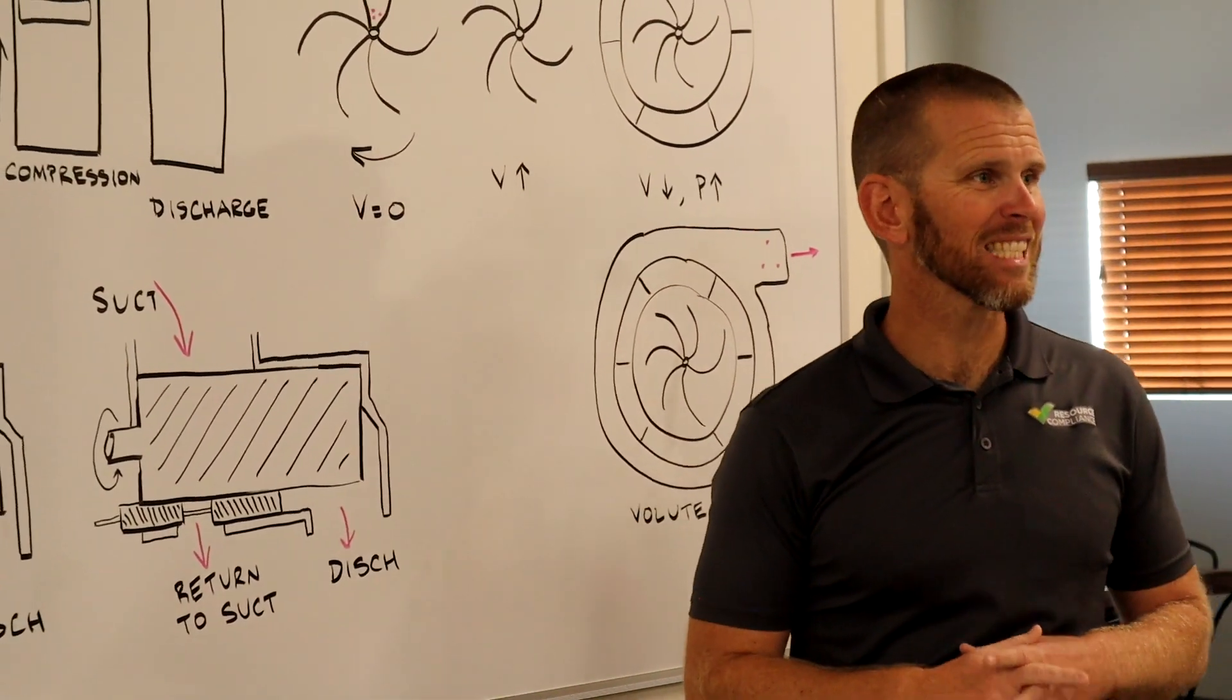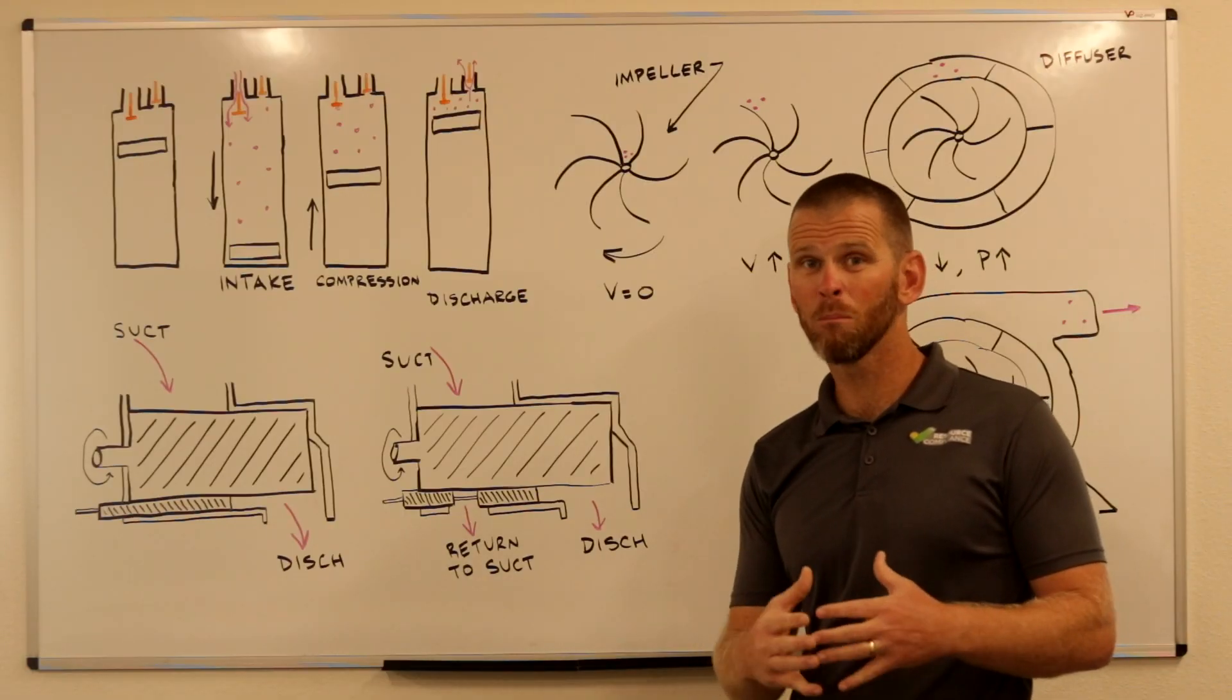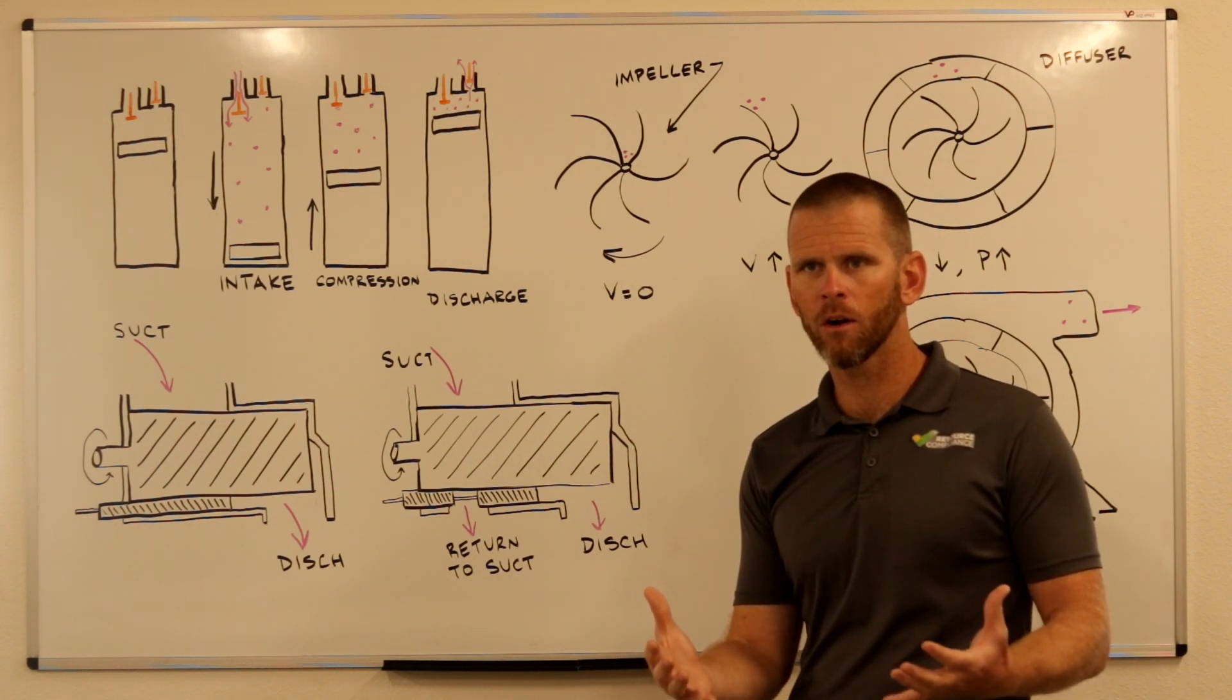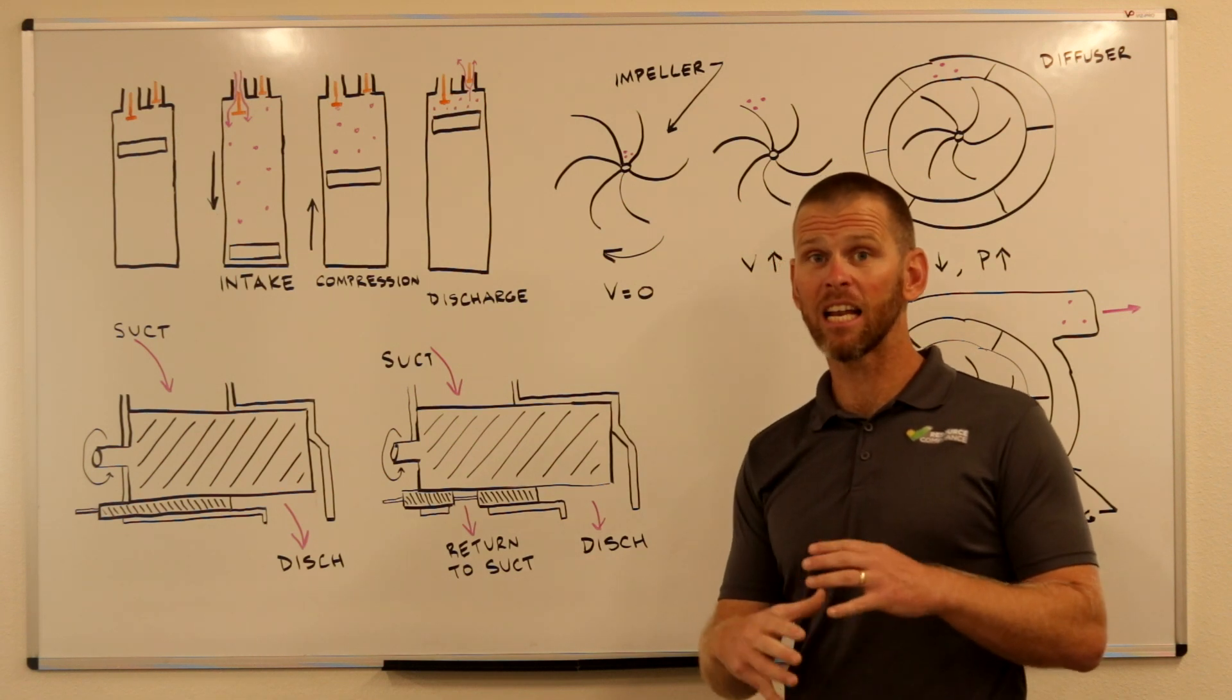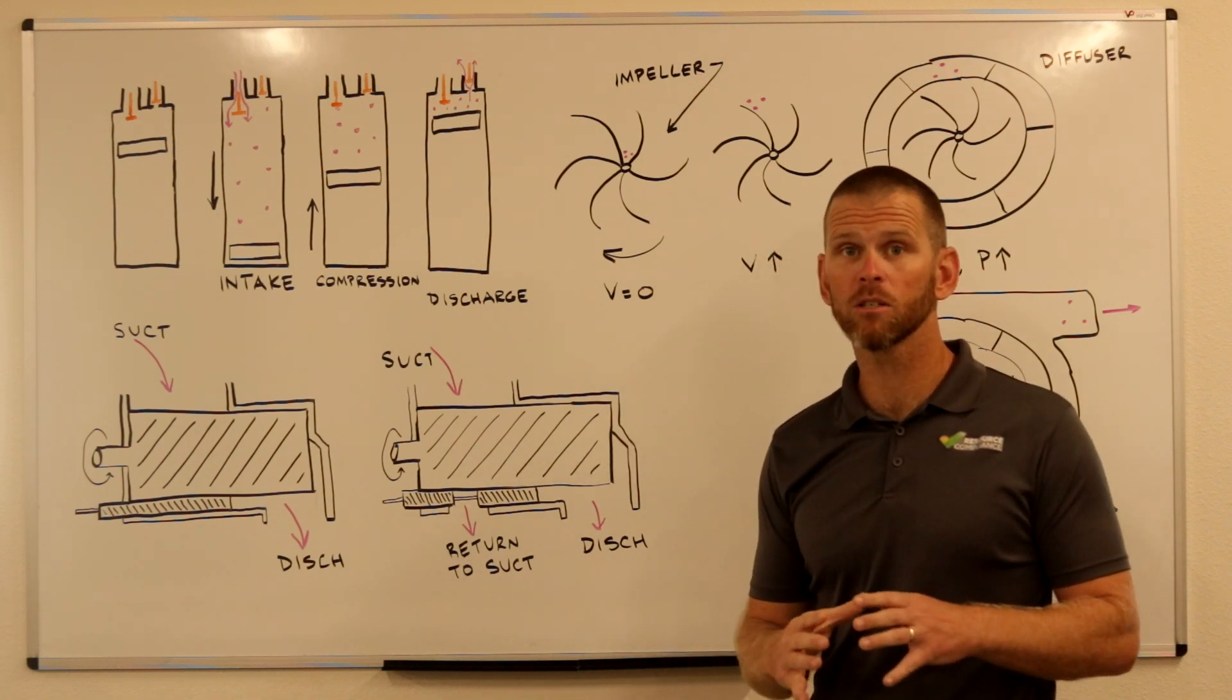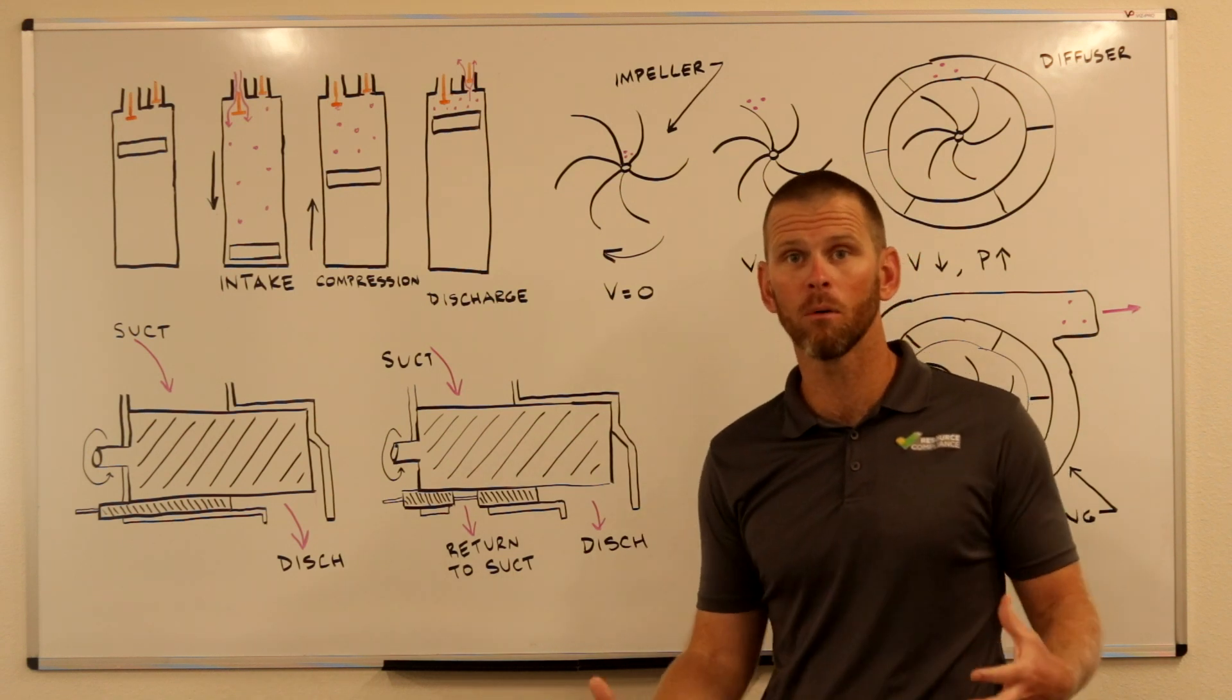It's similar to forcing the suction valve open in a reciprocating compressor. But by moving that slide all the way to the right and sealing that off now, there is no trap door available anymore, so we'd be getting full compression. When we're talking about slide valves, they're usually monitored by the percentage that they are closing the opening. If a slide valve is at 100%, that means the compressor is operating at full capacity or its full compressing potential.